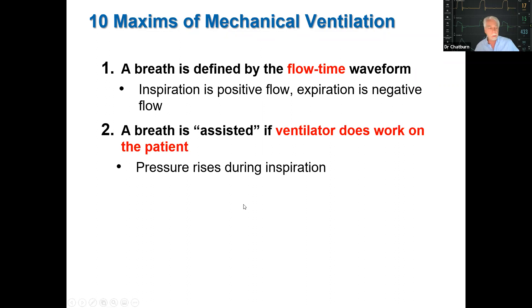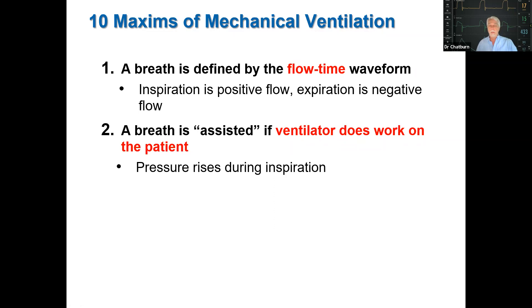Another term often misunderstood in clinical literature is the word 'assisted.' Manufacturers sometimes suggest a breath is assisted if the patient triggers it, mixing up 'assist' and 'trigger.' But assisting really means the ventilator does some work on the patient. How do you know? Pressure rises during inspiration — which is positive flow. If you force gas into the patient's respiratory system and pressure rises, that does work. Work is a function of both volume change and pressure change.